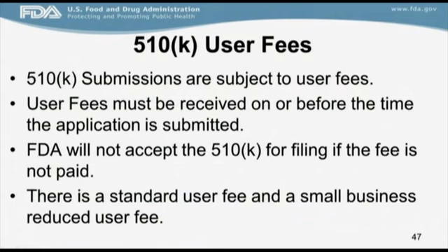Also, before you submit your 510K, you have to submit your user fee. 510K submissions are subject to user fees. Your user fee must be received on or before the time the application is submitted. FDA will not accept the 510K for filing if the fee is not paid. There is a standard user fee and a small business reduced user fee.